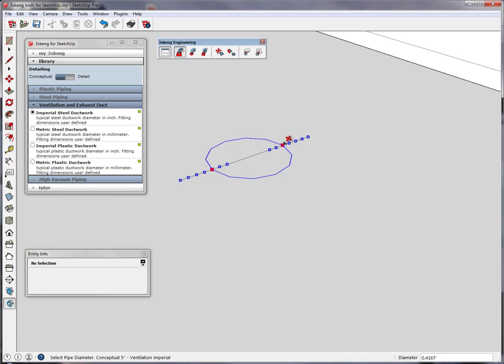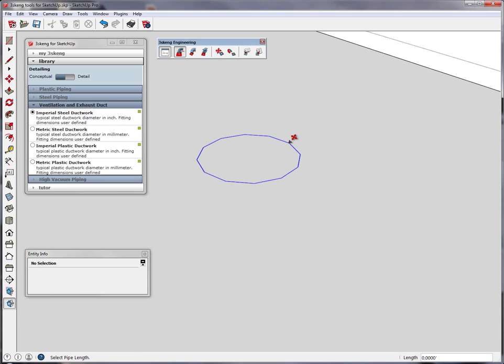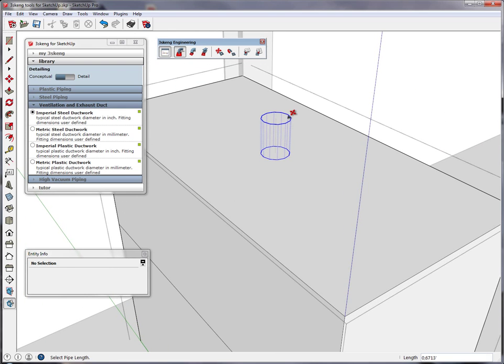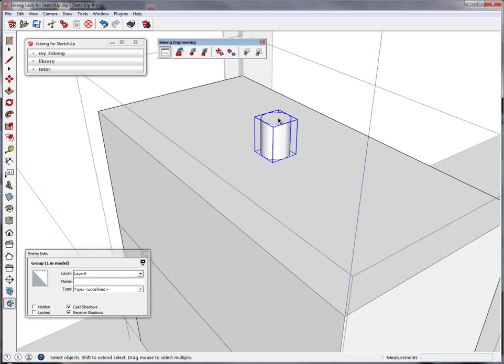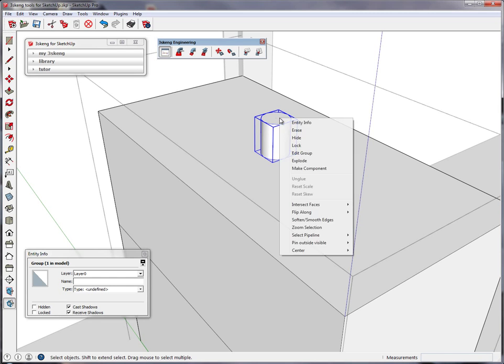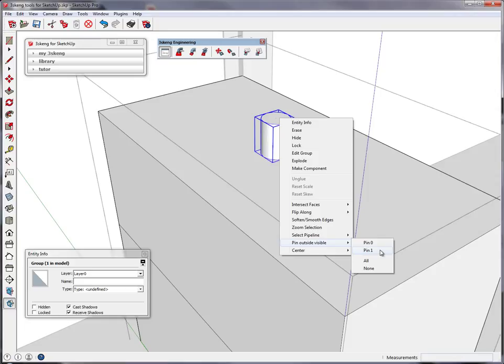Zoom in to get a better overview and we select 5 inch. By clicking, you can now indicate the length, which is random in this case. Now, very important: you click on this piece of pipe, make a right click, hover down to Pin Outside Visible and activate Pin 1. Pin 0 is always your starting pin, and Pin 1, which is the end of our pipe, being visible outside the component means that 3skeng tools recognize this pin as one they can attach to.